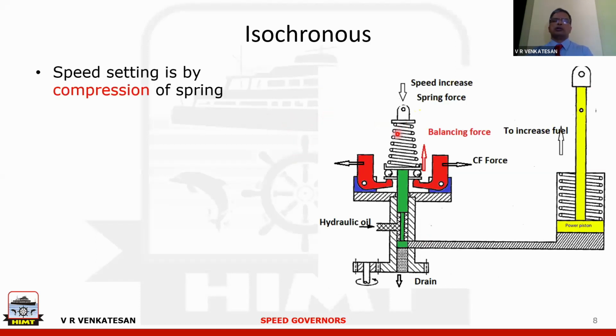This is the spring, centrifugal governor speeder spring, we call it. The spring force is adjusted by the motor on top. The governor works by the principle that this entire mechanism is driven, rotation you can see, and these are the flyweights which are going to be going around, and this centrifugal force acting on the flyweight acts this way. So there are two forces which are being balanced.